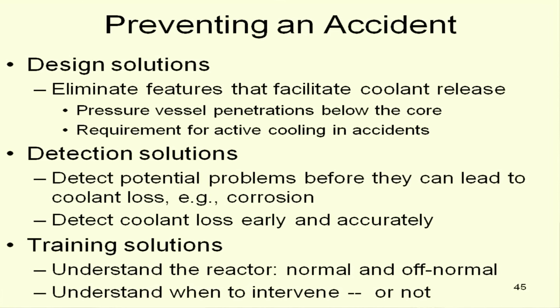You need to be able to detect coolant loss early and accurately. And in Three Mile Island, you might remember some years ago, and in some of the Japanese reactors, in both cases, they were having a lot of difficulty figuring out exactly what the water level is. Is the core uncovered or is it not? It's just that kind of information, and that detection, which is more instrumentation, needs to be coupled with training solutions, which is understanding the reactor in both normal and off-normal situations and when to intervene or not.